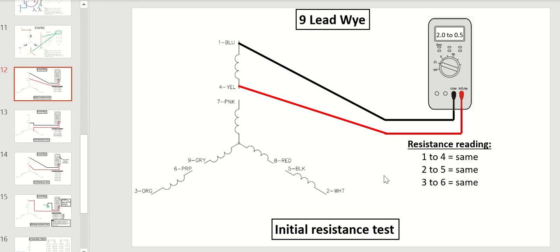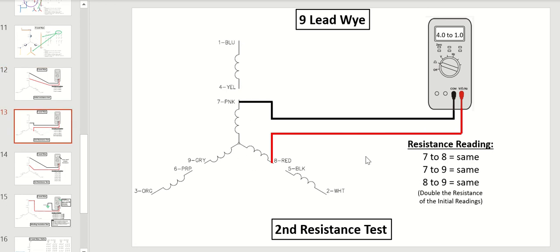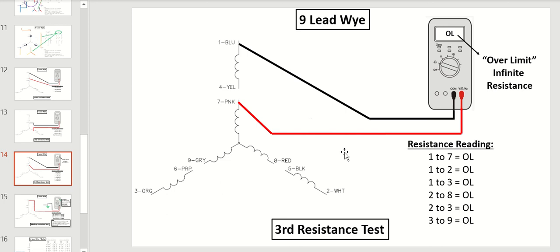Testing is basically the same. You just want to make sure that you have the same resistance across each one of these windings. When you get to this junction here, where you've got 3 windings to a common junction, you want to test those and make sure all those are the same. Obviously the resistance here should be about double the resistance that you took on the first 3 readings. The third resistance test is to make sure that there's no short between any of the windings, and that you can do by following this information here.